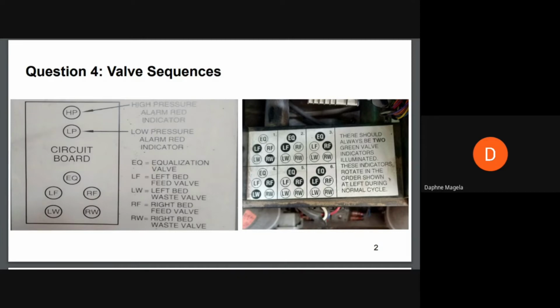When the equalizer valve is on, the pressure is shared between the two sieve beds. That means if the pressure was 30 psi when sieve bed A was being fed, the pressure in the two beds would be 15 psi. The equalizer is on for a period of 2 seconds. After that, the equalizer valve closes and the waste valve for sieve bed A is turned on. The equalizer valve is also known as the pressure equalization valve because what it actually equalizes is the pressure in the sieve beds. But other concentrators, like you mentioned, the DeVilbiss, do not have equalization valves.